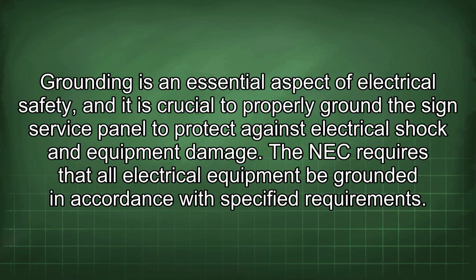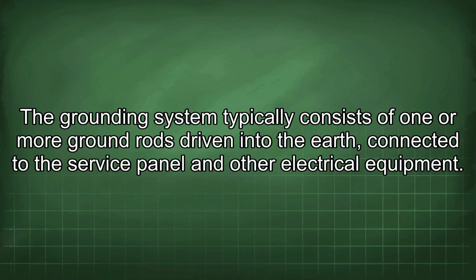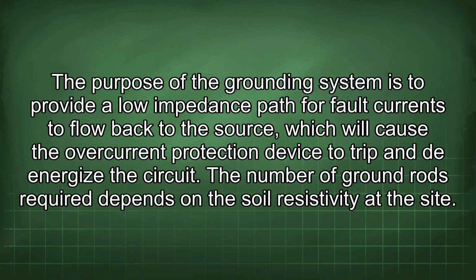Grounding is an essential aspect of electrical safety, and it is crucial to properly ground the sign service panel to protect against electrical shock and equipment damage. The NEC requires that all electrical equipment be grounded in accordance with specified requirements. The grounding system typically consists of 1 or more ground rods driven into the earth, connected to the service panel and other electrical equipment. The purpose of the grounding system is to provide a low impedance path for fault currents to flow back to the source, which will cause the overcurrent protection device to trip and de-energize the circuit.